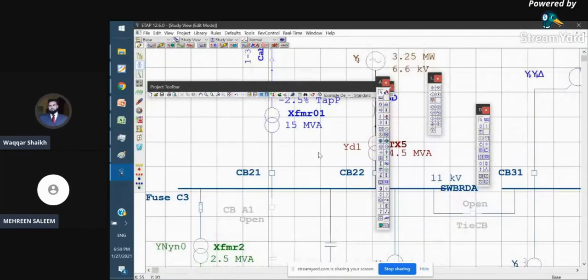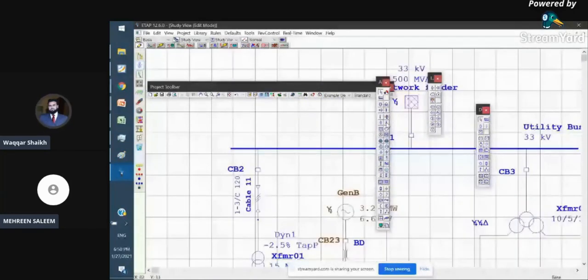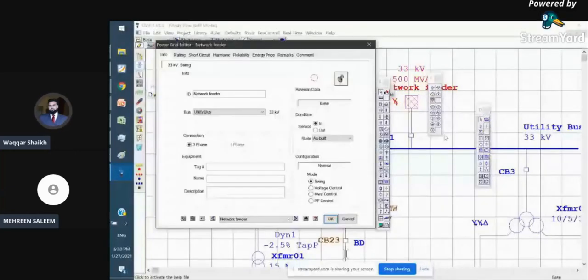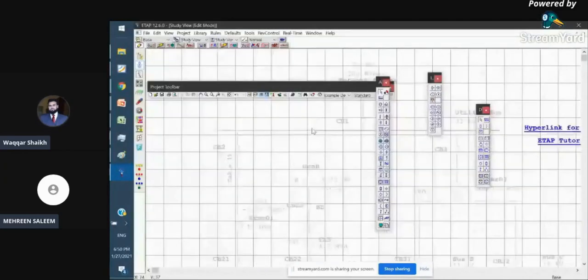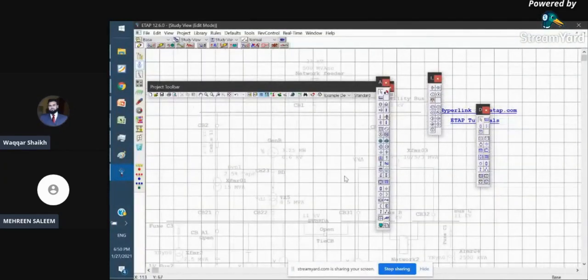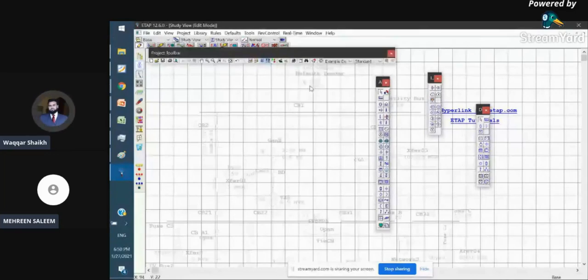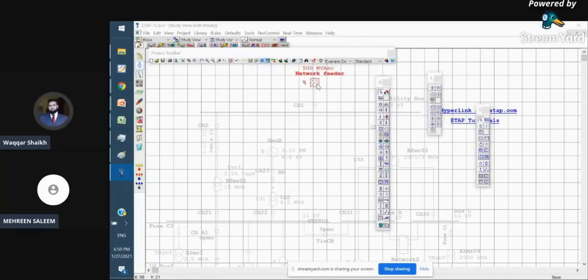Let me give you an example: in this case, the swing source is this utility. If I disable this feature and make it a voltage control source instead, the whole network will be de-energized. Power system analysis students would have studied that a swing bus is like a reference bus, slack bus, or infinite power bus, which enables us to run simulations and load flow solutions.